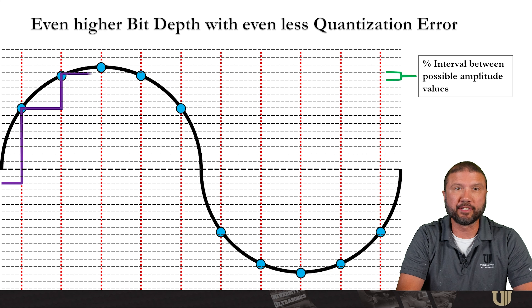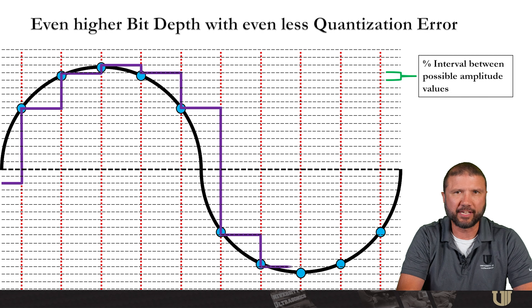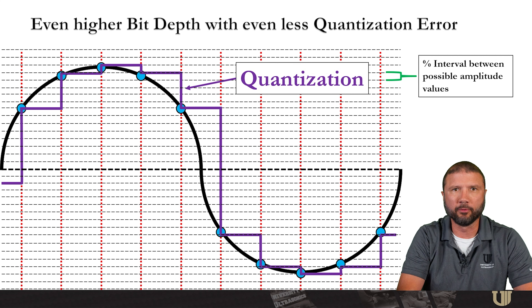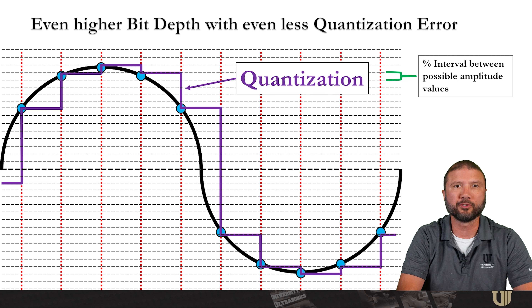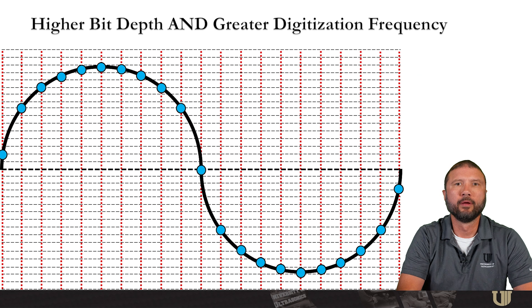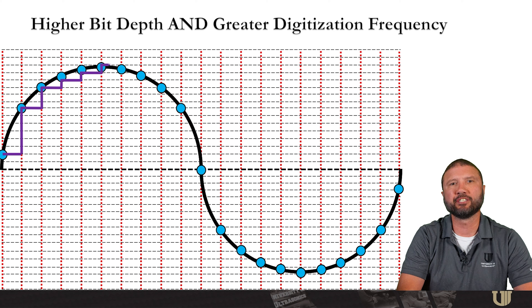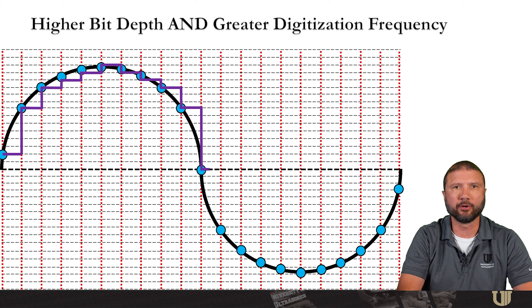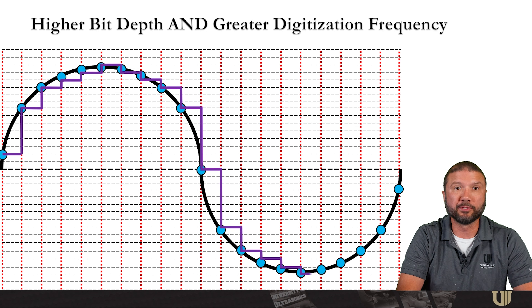Now we've increased the number of possible amplitude values even more by using a higher bit depth. Not every sample lands directly on a possible value, so there will still be some error. But the interval between possible values is getting smaller and smaller, meaning my quantization error also gets smaller. If we increase both bit depth and digitization frequency, the digital version of the waveform will get closer and closer to matching the original analog. But with more precision, the result is a larger data file and a slower scanning speed.